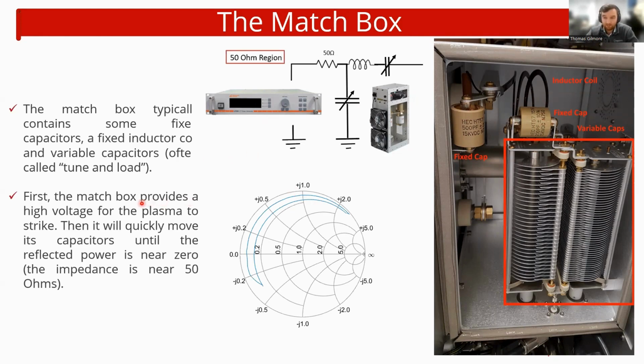Do note that the matchbox has multiple jobs. It's not just to match the impedance of the plasma. You also have to strike the plasma, and to strike it you need to reach what's called the breakdown voltage. So the matchbox also needs to initially provide a high enough voltage to strike the plasma, and then it changes its position in order to keep power delivery at maximum.